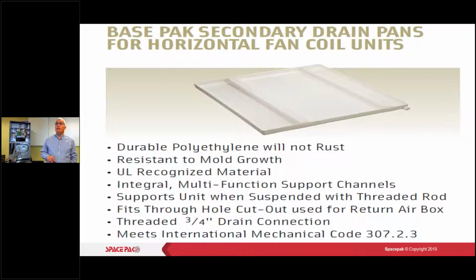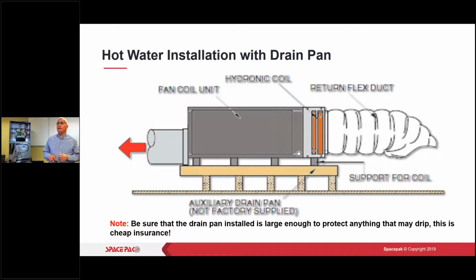We do have these base pans for you for our horizontal coils. We've changed the material, so it's not going to rust. It's a polyethylene. It's resistant to mold. It's going to support the unit, but the unit's really supported by threaded rod. I misspoke there. Be aware of that. This is not there to support the unit. So here's a spec to show you how that drain pan is installed.